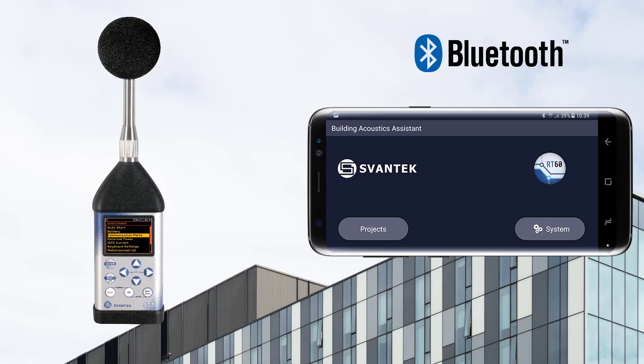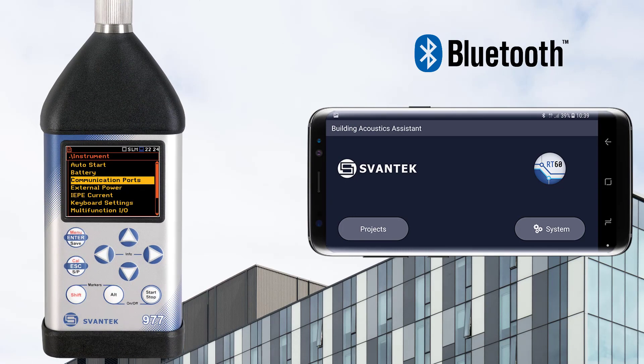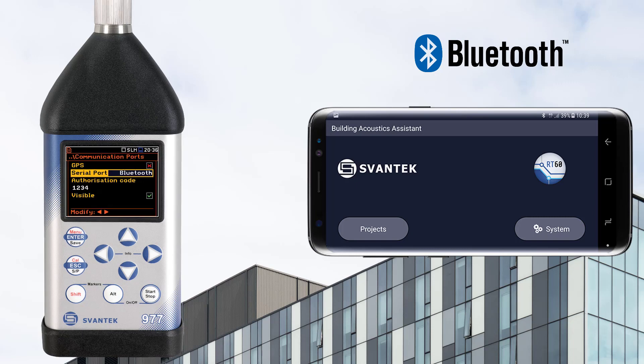To establish a connection, make sure that Bluetooth is selected on your Sound Level Meter. For example, with the Svantek 977A instrument, go to Communication Ports and choose Serial Port Bluetooth.